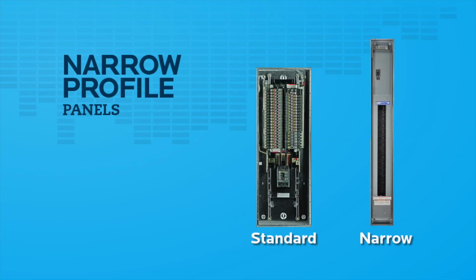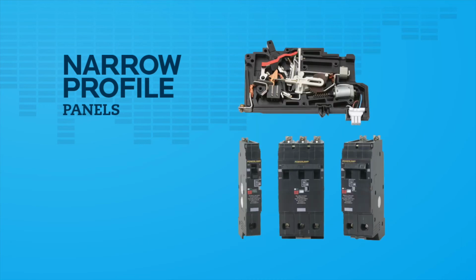For hardware, the narrow panel utilizes Square D's industry-leading PowerLink platform and comes in a 9-inch wide enclosure compared to the traditional 20-inch wide enclosure for a circuit breaker panel, and can hold either 30 or 42 circuit breakers per panel. Circuit breakers are rated for 200,000 on, off, on operational cycles at a full electrical load and are available in 15, 20, and 30 amp ratings with single, 2-pole, or 3-pole configurations available.